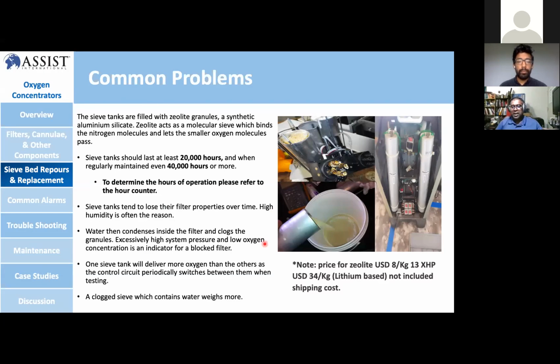So with water, areas with water, all that, you need to be careful, because the oxygen concentrator tends to absorb this humidity into the system, and the sieve tank doesn't perform very well during that period of time, and the lifespan can reduce. So always make sure that the area is dry and clean. Sometimes you get one sieve tank not performing while the other is working. You cannot replace just one, you need to replace both actually. So you need to check that particular part.